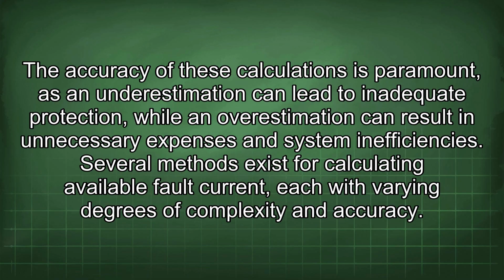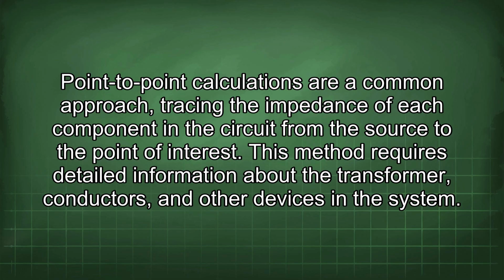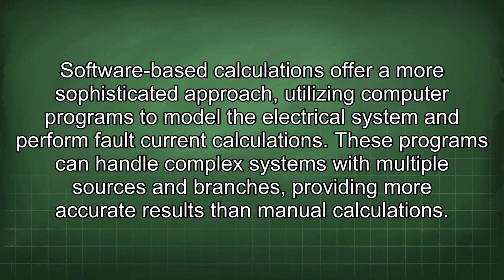Several methods exist for calculating available fault current, each with varying degrees of complexity and accuracy. Point-to-point calculations are a common approach, tracing the impedance of each component in the circuit from the source to the point of interest. This method requires detailed information about the transformer, conductors, and other devices in the system. Software-based calculations offer a more sophisticated approach, utilizing computer programs to model the electrical system and perform fault current calculations. These programs can handle complex systems with multiple sources and branches, providing more accurate results than manual calculations.